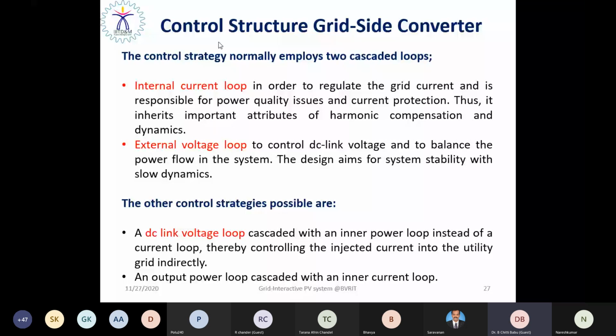As for the DC link voltage control, it has to be maintained constant while transferring power from solar PV to the utility grid, right? As it contributes to maintaining the power flow between the source and the load, it contributes to the active power control, because active power control is very essential to maintain the frequency. Moreover, the voltage at the point of common coupling also has to be controlled, so that it can avoid unnecessary reactive power burden on the grid, and ensure unity power factor operation as well.